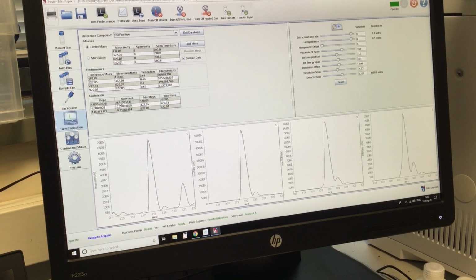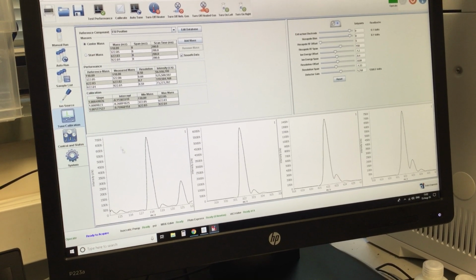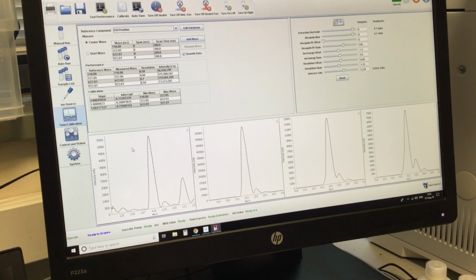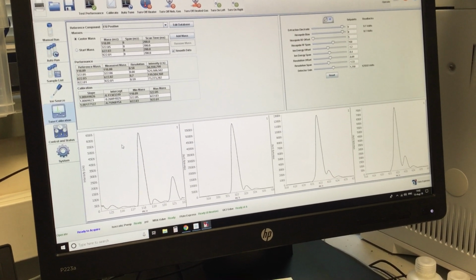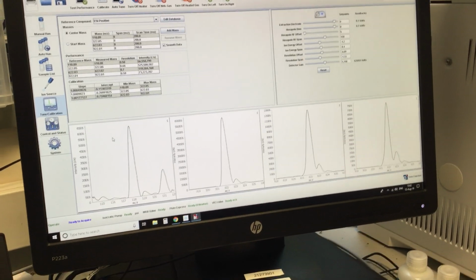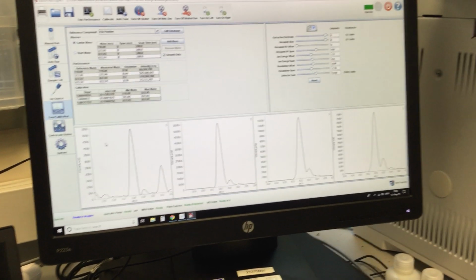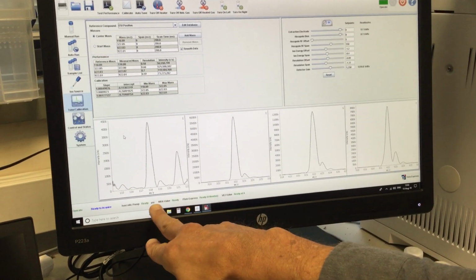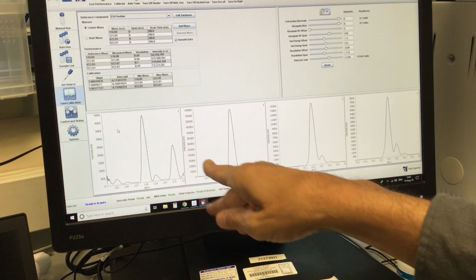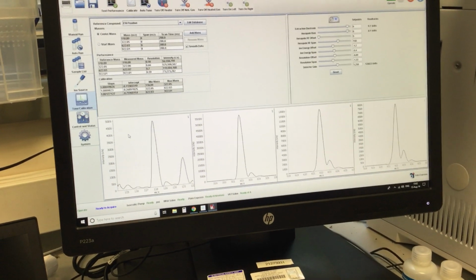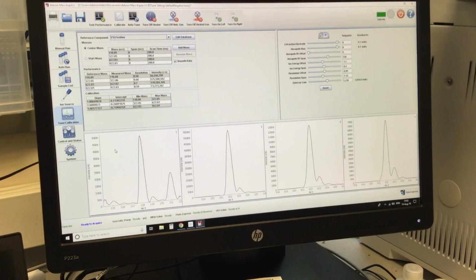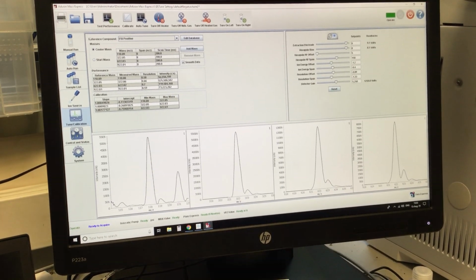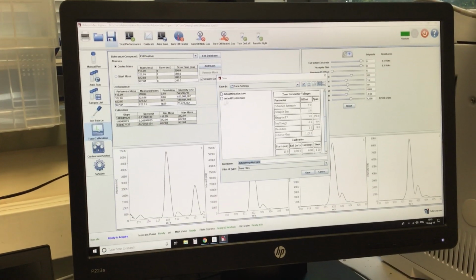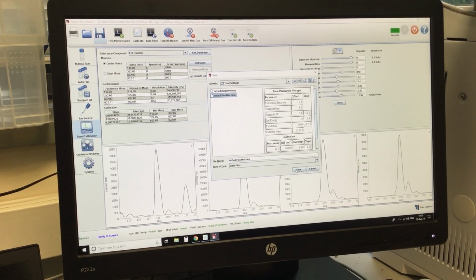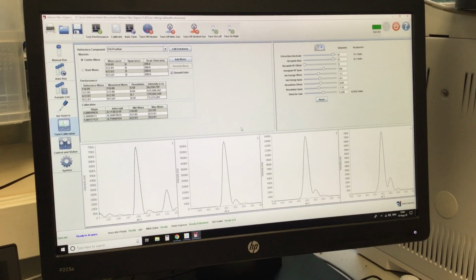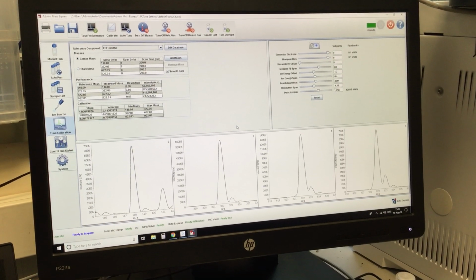So then it also completes this table here, and this you can see is just a mathematical correction really. It's just correcting for any slight differences in the physical characteristics of the mass spec, to make sure when it says it's 118.08 it is indeed 118.08. Yeah. So we've done the calibration, so now we have to save it, and that's going to be default positive. Okay, so that's all done.